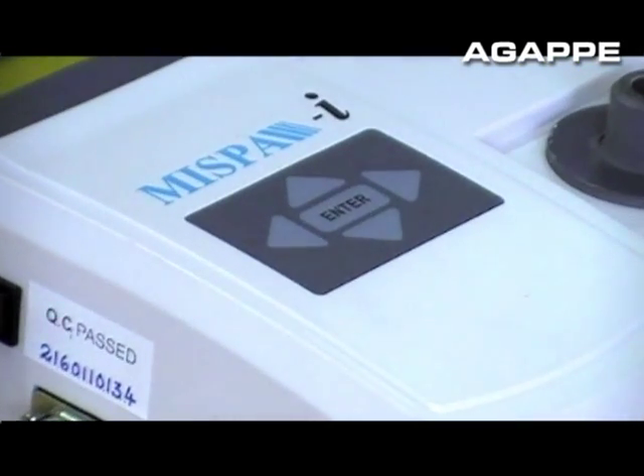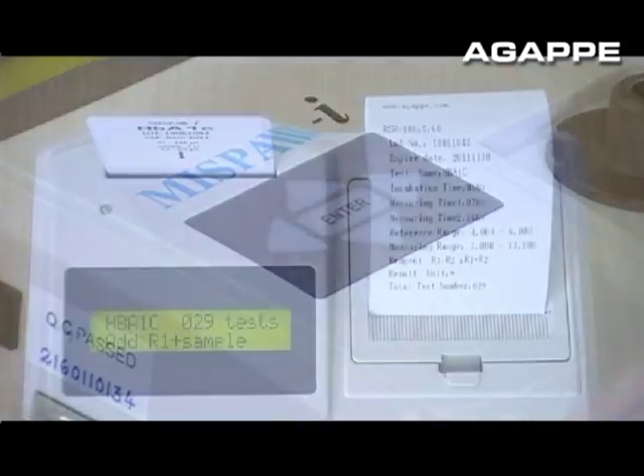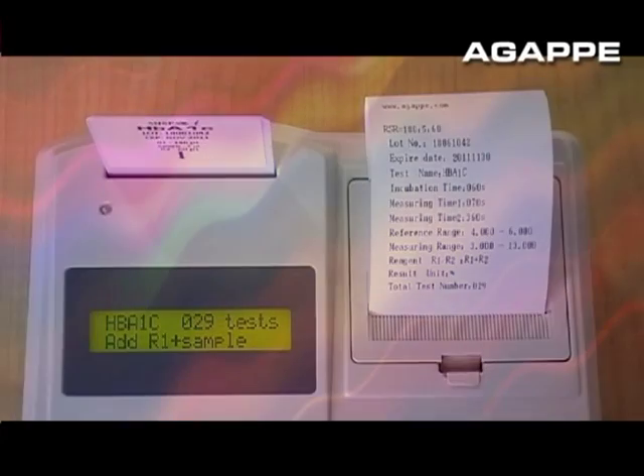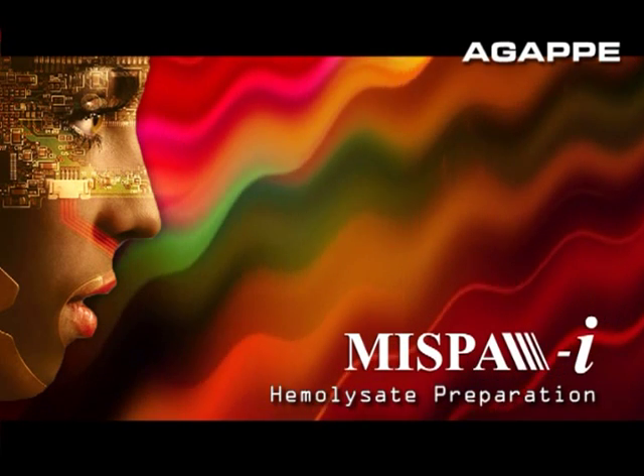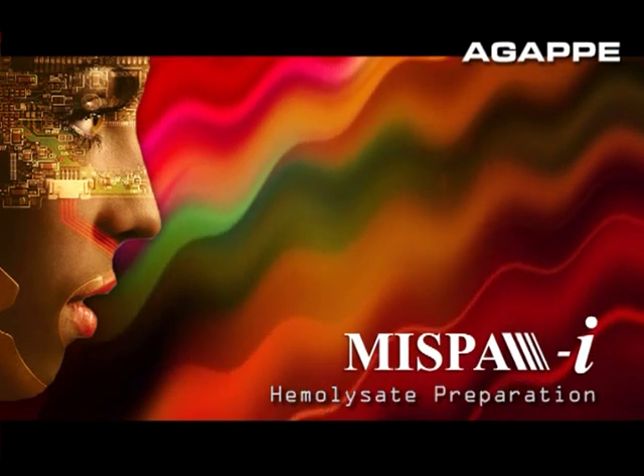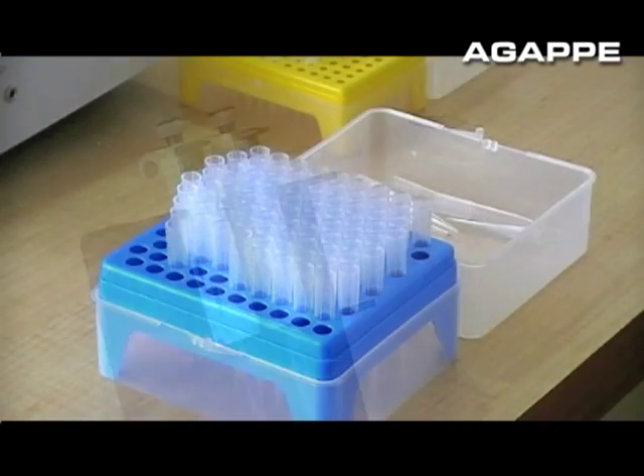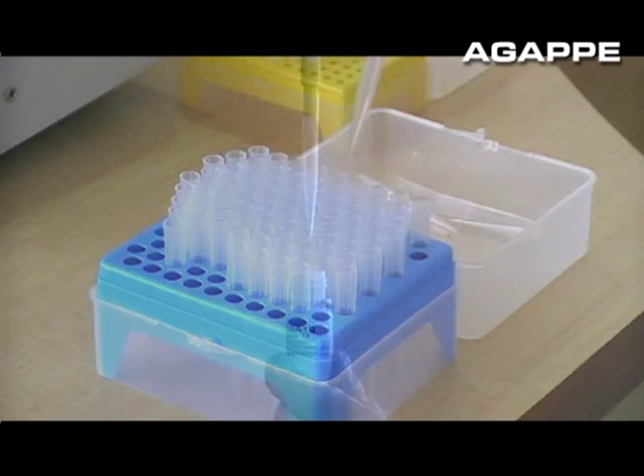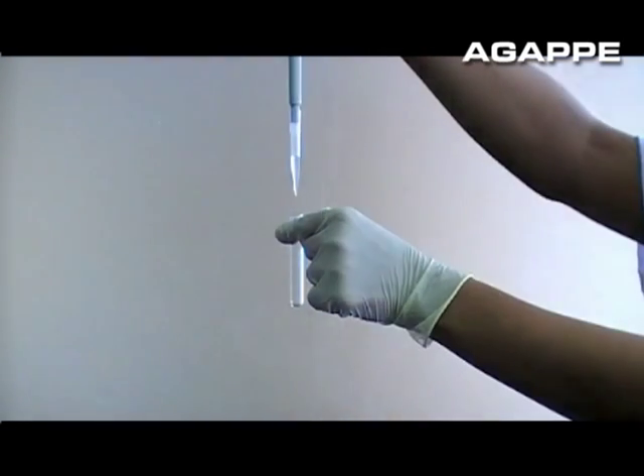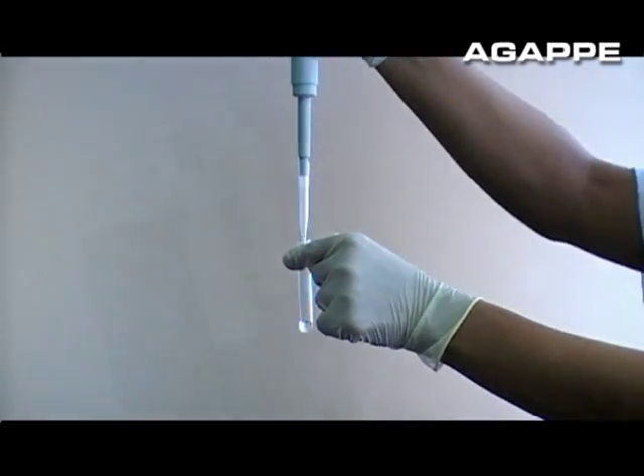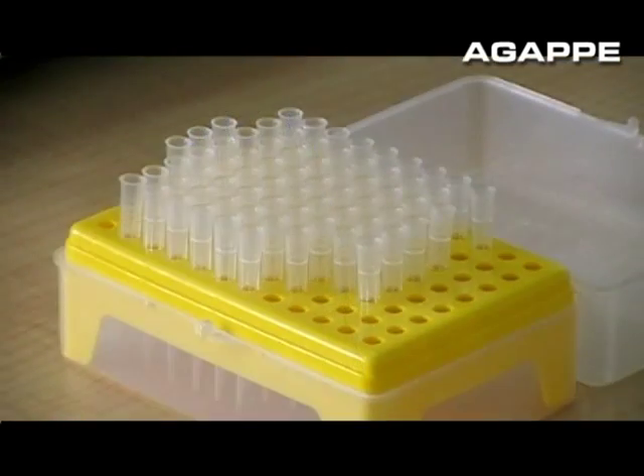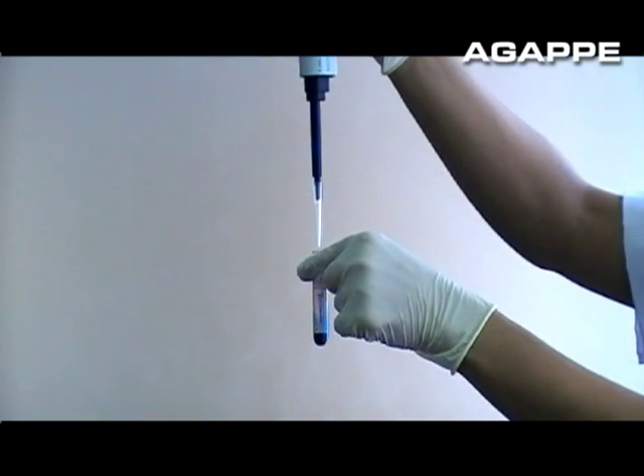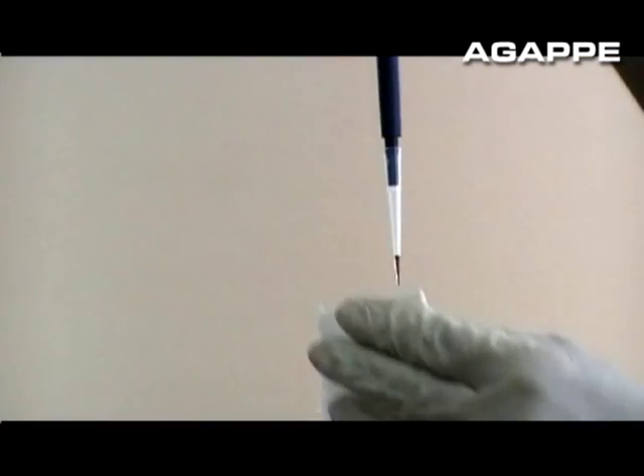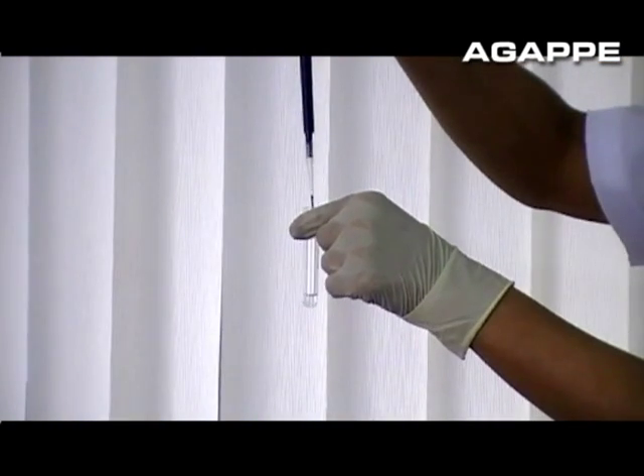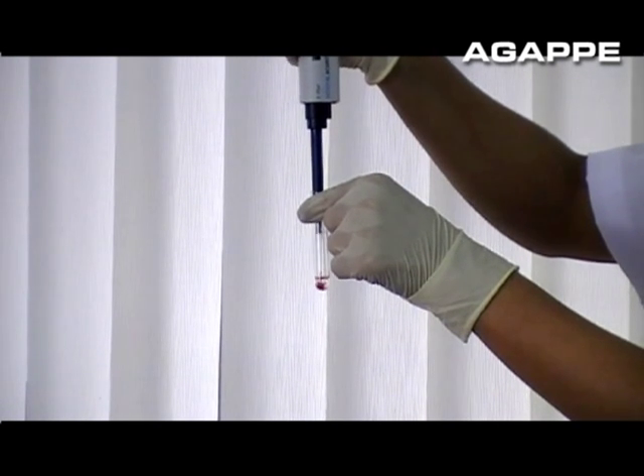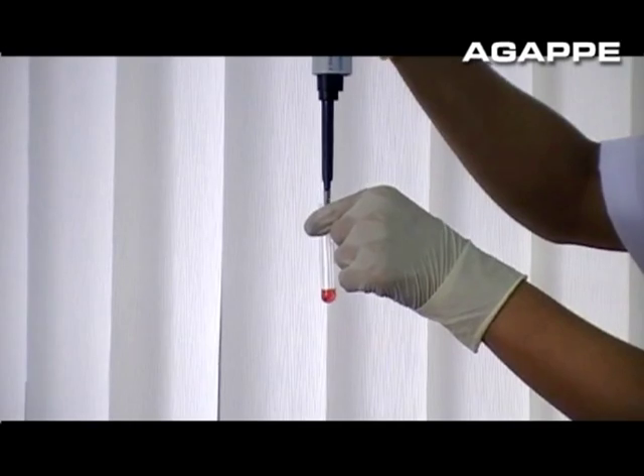To continue the test, press Enter. Then the display will prompt you to add both R1 reagent and sample. For the HbA1c test, prepare hemolysate. Now, we will show you how to do that. Dispense 500 microliter hemolyzing reagent R3 into a clean test tube. Then dispense 10 microliter of whole blood sample into the same test tube. Wait about 10 minutes for hemolysation and use it before 3 hours.